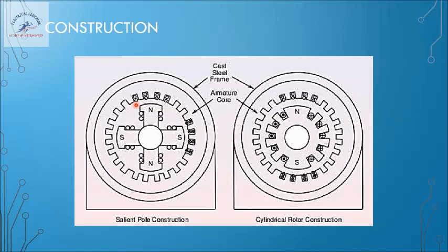So the stator consists of steel laminations, silicon steel or cold rolled grain oriented steel lamination structures. We call it a yoke. There are stator conductors forming the armature, and this is where we give supply, which is three-phase AC supply. So three-phase AC supply is given to the stator windings. So there will be stator windings, which is usually a three-phase distributed winding.